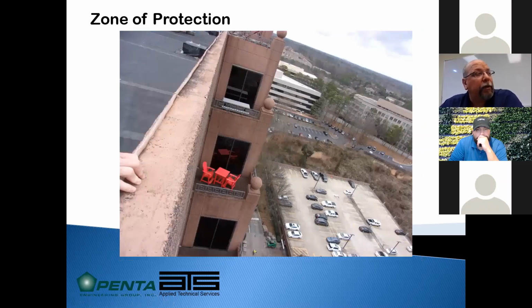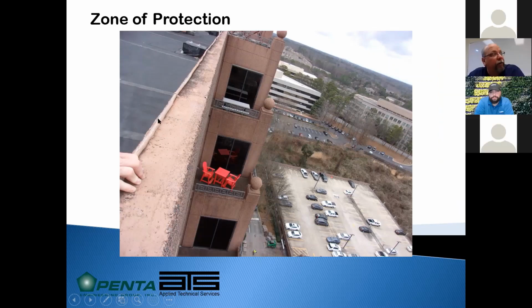Another area we see a lot of issues with is with tall buildings and balcony levels. If you have a building that's over 125 to 150 feet, that rolling sphere is going to go straight down the side of the building. So anything that juts out needs protection. In this case, this was an 18-story building, more than 150 foot tall. So from this level, the sphere would just roll straight down. So we need lightning protection out here on this outer perimeter of these balconies.